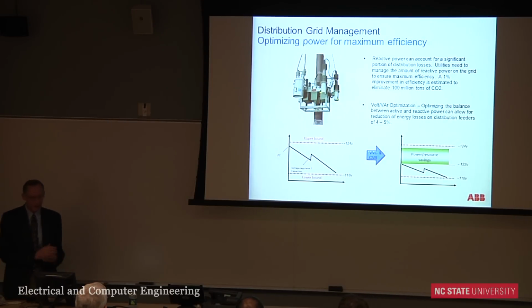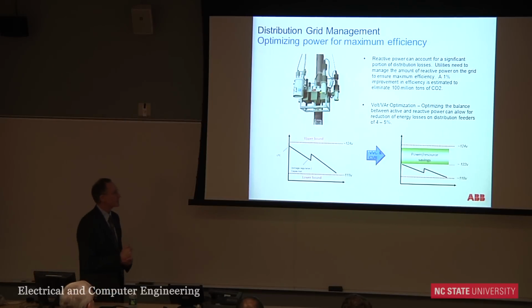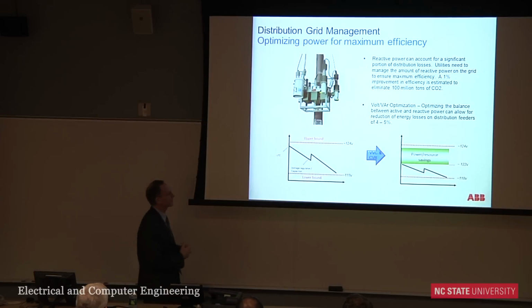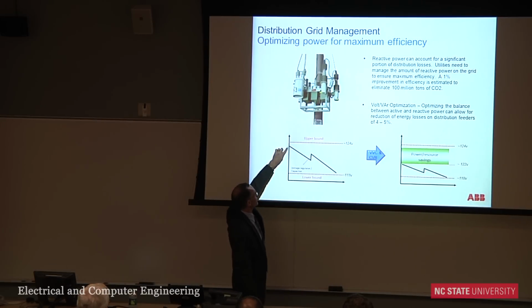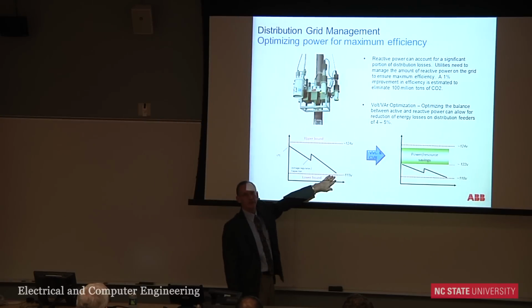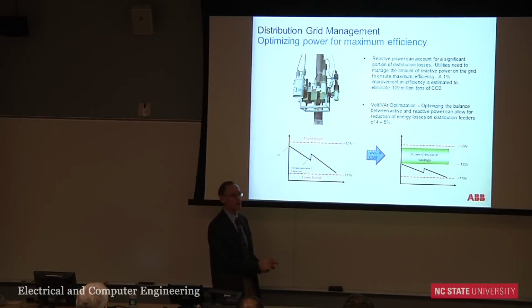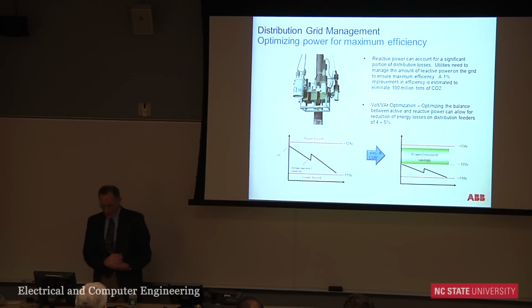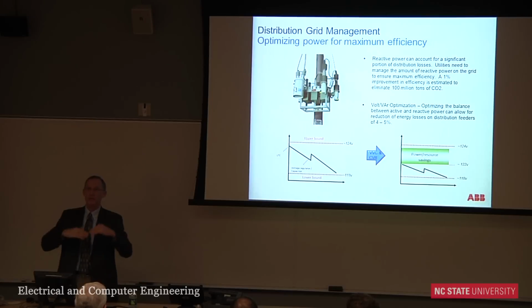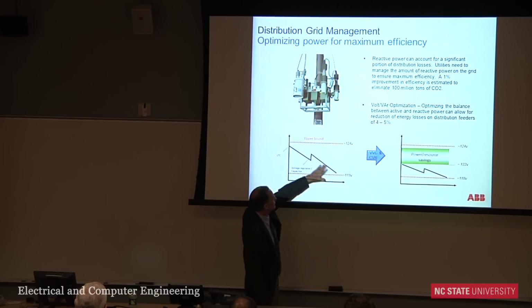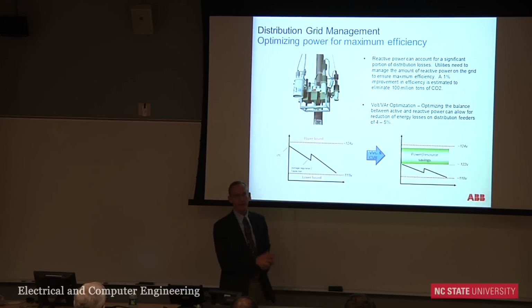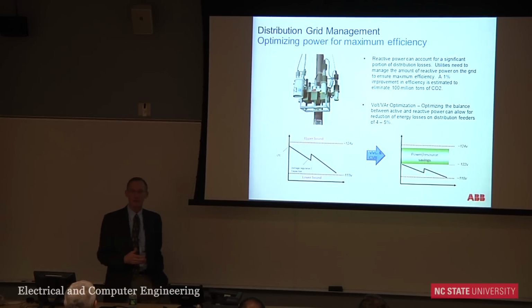I also mentioned the VoltVar controller, for VoltVar optimization. Basically, with feeders, in this simplified diagram, voltage is higher at the substation than at the end of the feeder. Utilities have for years used line voltage regulators and capacitor banks to raise the voltage along the feeder, reducing this voltage regulation, meaning the drop from substation to the end of the feeder, to make the curve more horizontal. In doing so, particularly using capacitor banks to offset the inductance of motors and of the lines, you become more efficient.